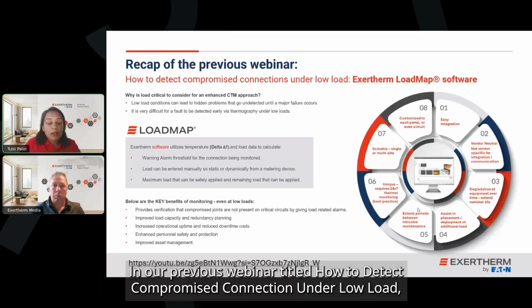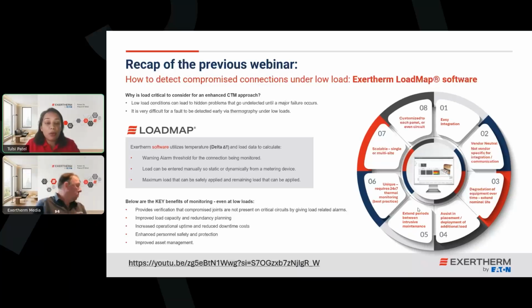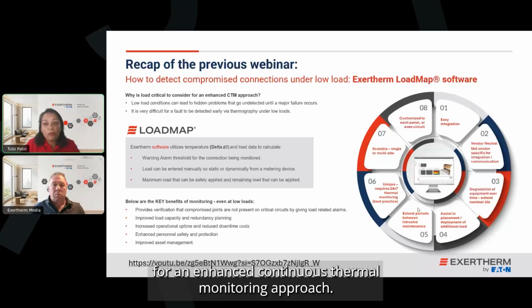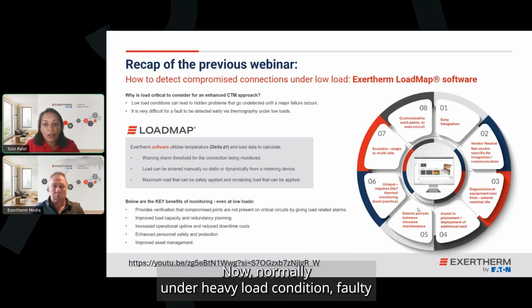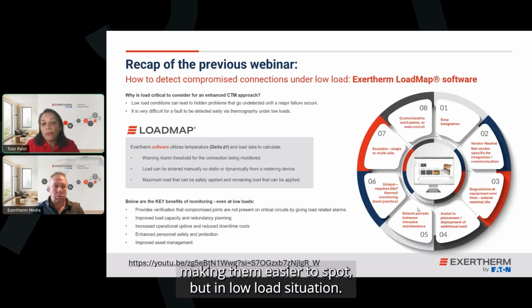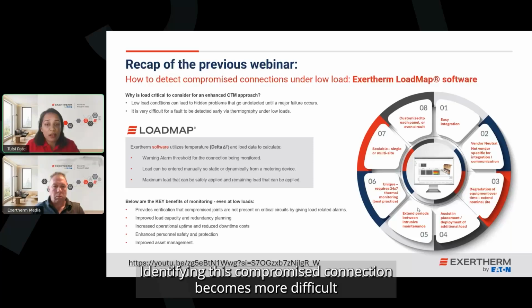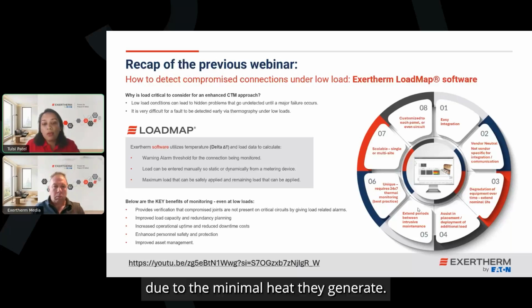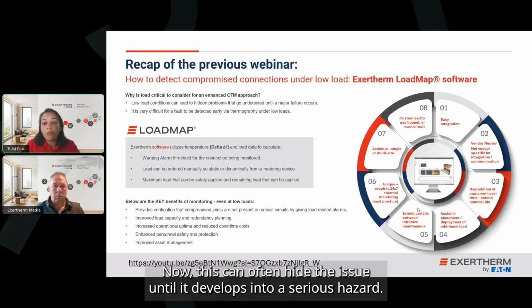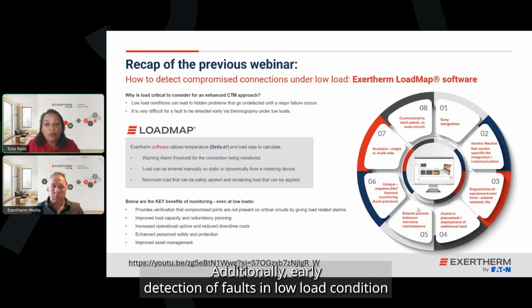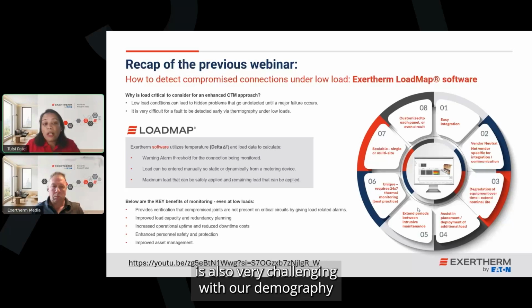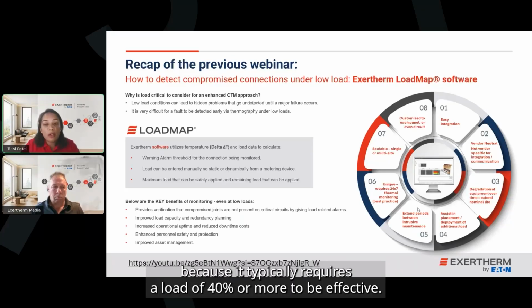In our previous webinar titled How to Detect Compromised Connection Under Low Load, we highlighted the importance of considering load for an enhanced continuous thermal monitoring approach. Now, normally under heavy load condition, faulty electrical connections tend to produce noticeable heat, making them easier to spot. But in low load situation, identifying these compromised connections becomes more difficult due to the minimal heat they generate. Now, this can often hide the issue until it develops into a serious hazard. Additionally, early detection of faults in low load condition is also very challenging with IR thermography because it typically requires a load of 40% or more to be effective.